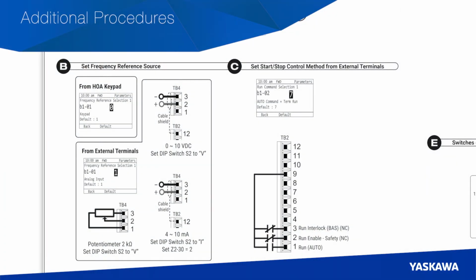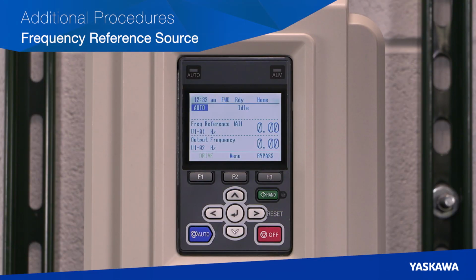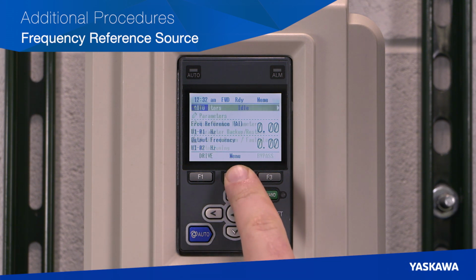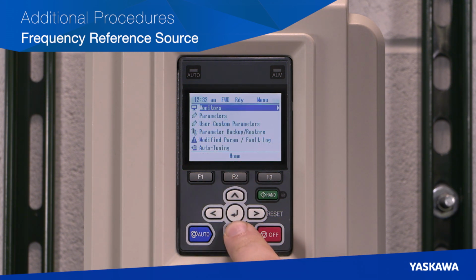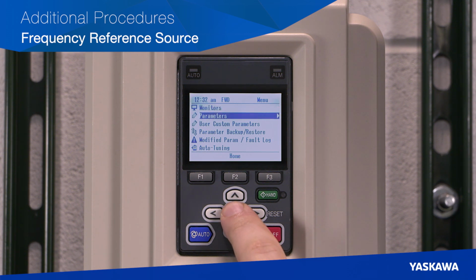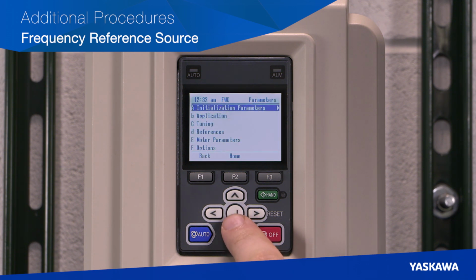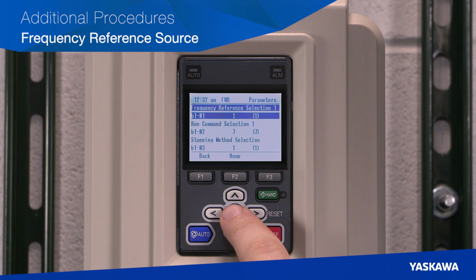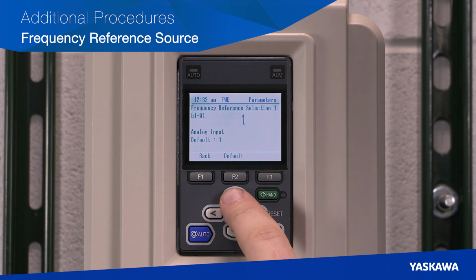Procedure B is for setting a frequency reference source. Navigate to parameter B101. This can be done by pressing the F2 menu button, then pressing the down arrow until you reach the Parameter menu. Press Enter and select the B Applications group. Then B1 Operation Mode selection. Press Enter and adjust B101 for your given application.